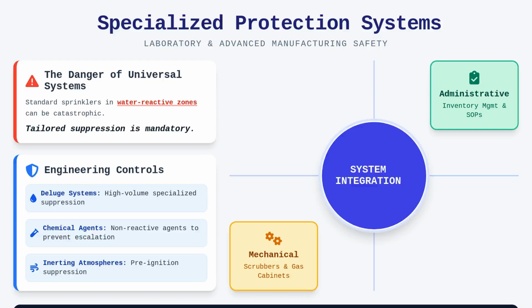The complexity of protecting modern laboratory environments or advanced manufacturing suites lies in the integration of specialized suppression systems. Unlike traditional sprinkler applications, hazardous material storage areas often require tailored suppression techniques, such as deluge systems or specialized chemical agent suppression that will not exacerbate the underlying chemical reactivity. For instance, attempting to extinguish a water-reactive fire with a standard automatic sprinkler system would be catastrophic, illustrating why we strictly forbid universal suppression strategies in these areas.